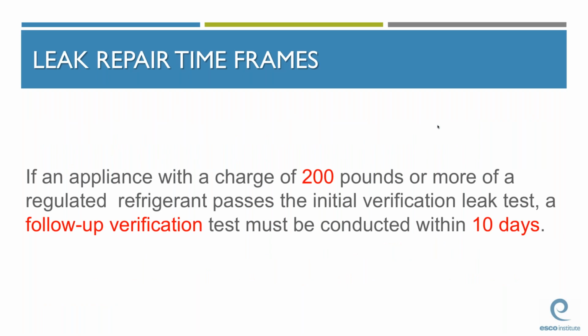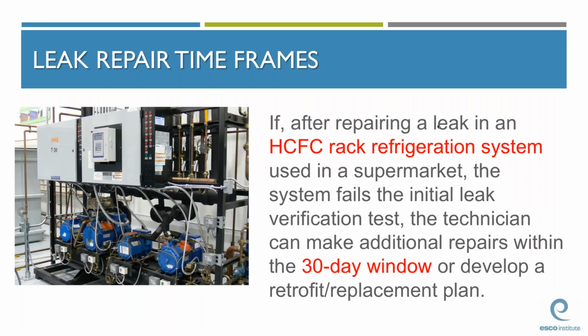So for example, if an appliance contains 200 pounds or more of a regulated refrigerant, a follow-up verification must be conducted within 10 days. This follow-up verification test is in addition to the initial verification leak test that was performed at the time the repair was performed. So we get this question a lot. If after repairing a leak, the system fails the initial leak verification test, the technician can make additional leak repairs within that same 30-day window. If repairs are not possible, then a system retrofit or replacement plan must be developed.